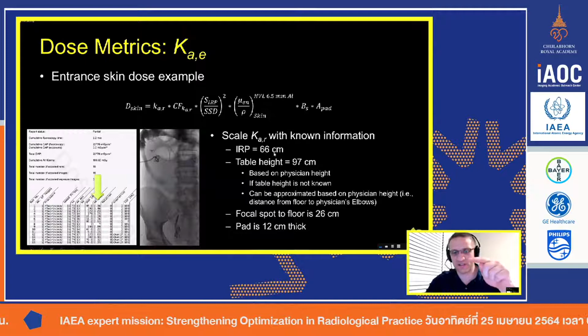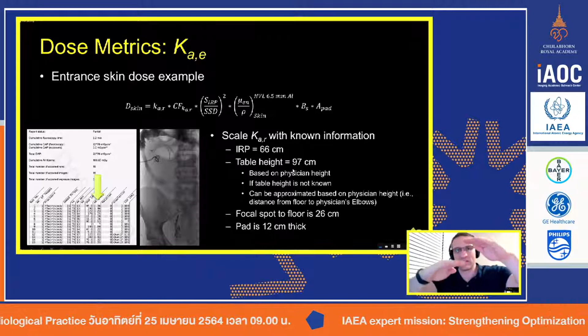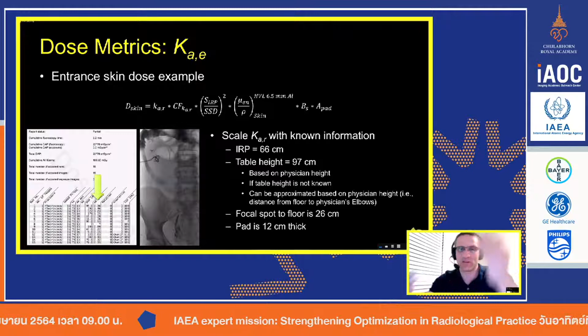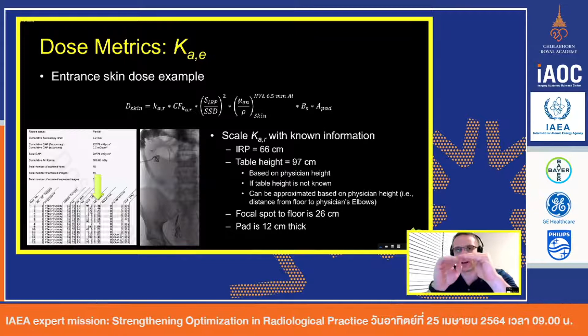All right, so my machine has a focal spot to floor distance of 26 centimeters. And so obviously I can do a little bit of math here. International reference point, 66 centimeters from the focal spot plus 26 centimeters. So that's 92 centimeters from the floor. So my international reference point is 92 centimeters. My table is 97 centimeters. So now I know that there's a 5 centimeter difference. So it's actually not at the entrance point of the body. I need to correct that.